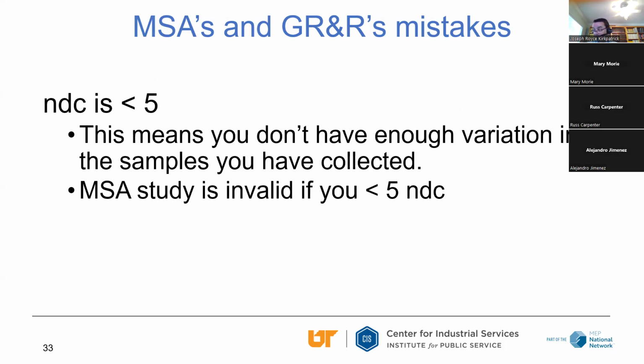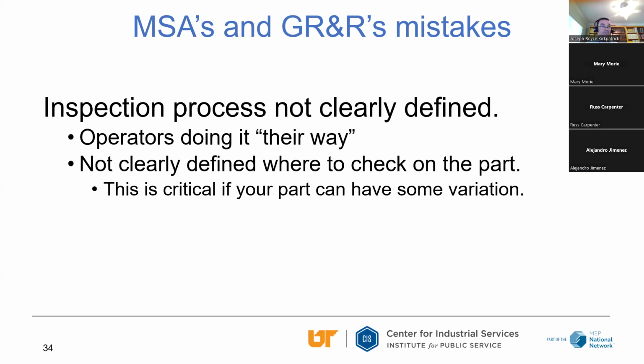That is one of the hardest parts about doing a gauge R&R study: getting the right samples. You can't just go out and grab 10 samples out of production and say these are the samples we're going to use, because most companies don't have that much variation in their normal production process. So you need to get with production and say, I need some parts on the high side, some on the low side, maybe some parts out of spec. You don't want to risk getting nonconforming product to the customer, but sometimes it's good to have a part out of spec for a gauge R&R, and that will increase your number of NDCs.